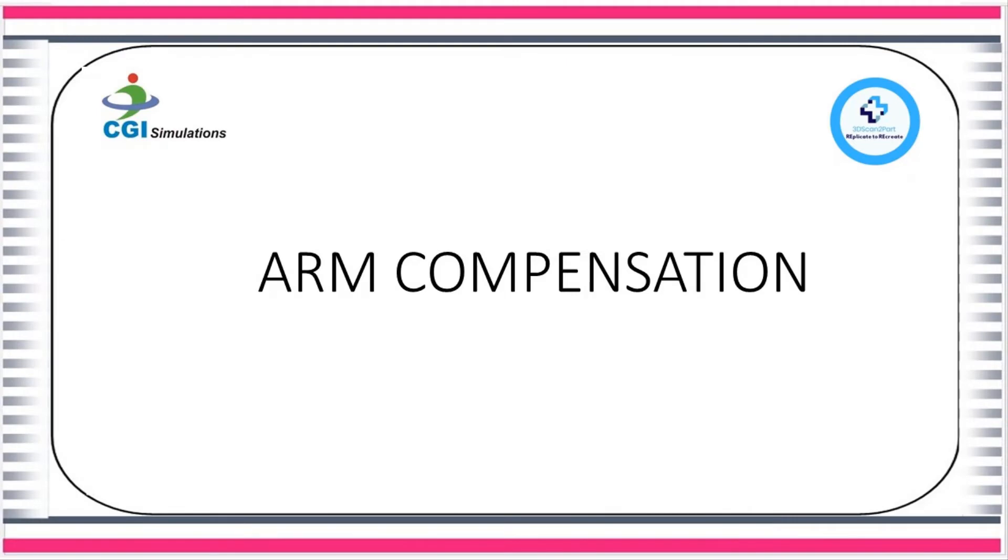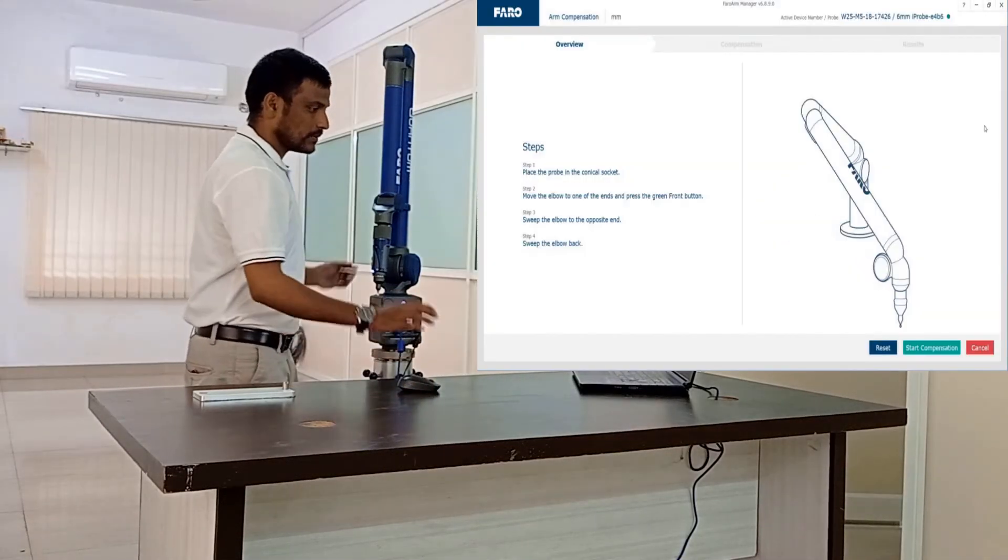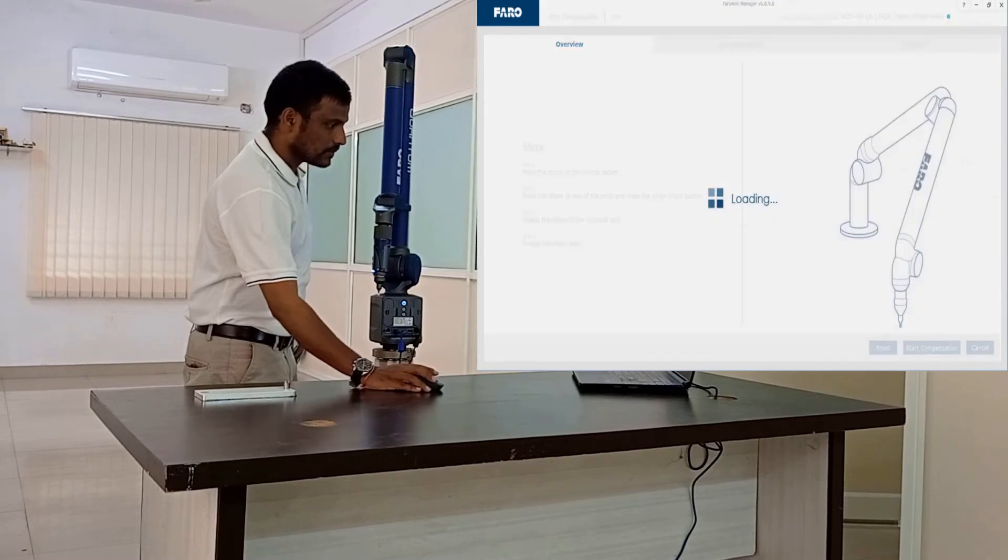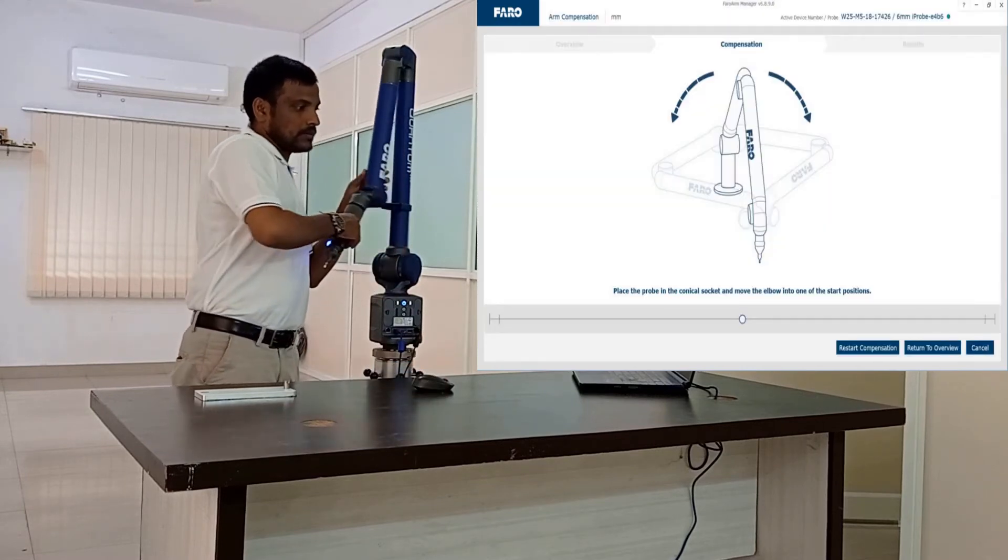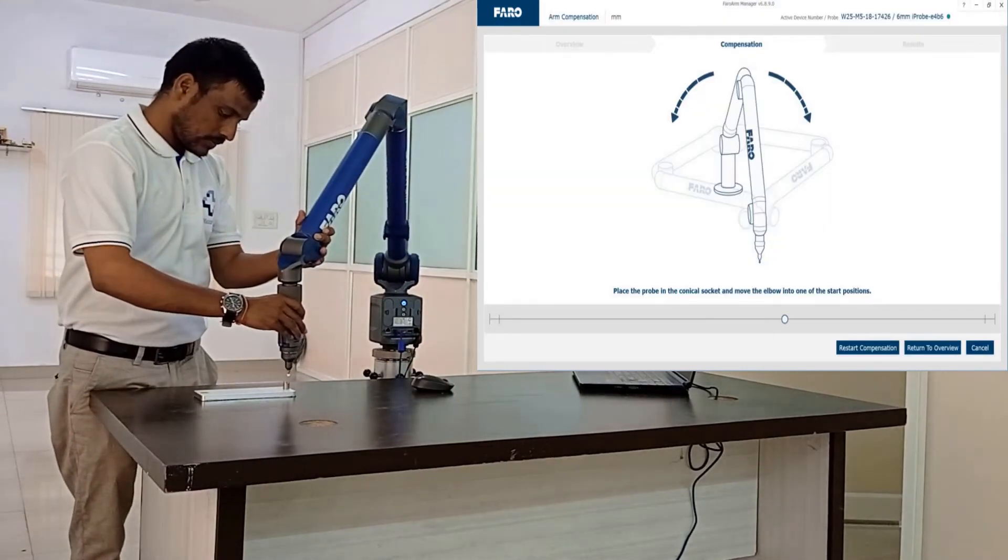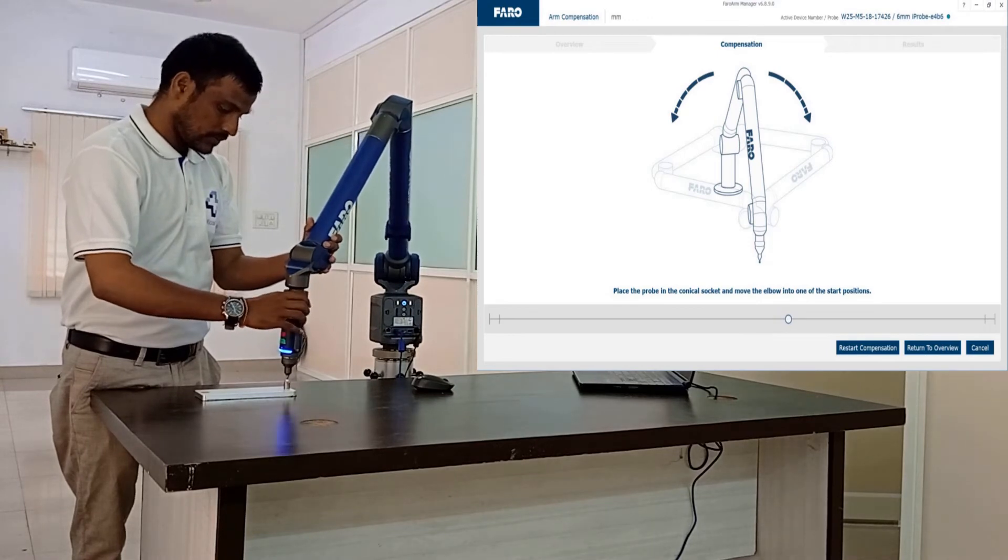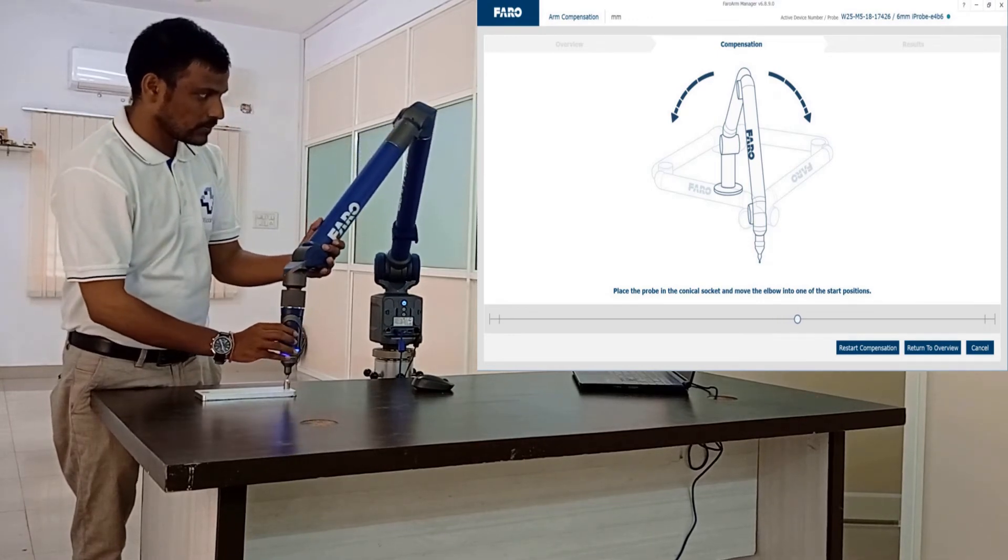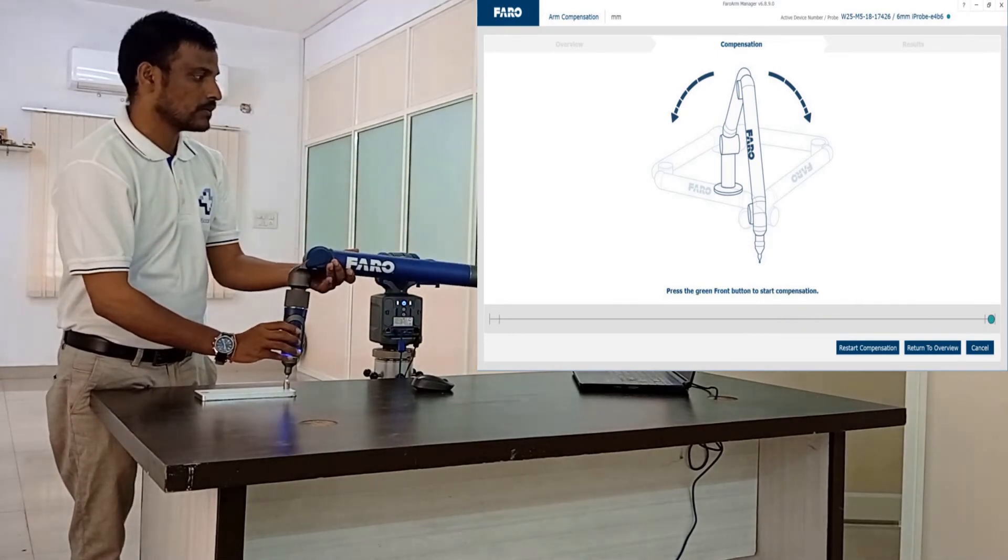Let us do arm compensation. In the Faro arm manager click on arm compensation. Place the probe in the conical socket and move the elbow to one of the ends. Till the green indicator on the laptop dialog box is dragged to the end.